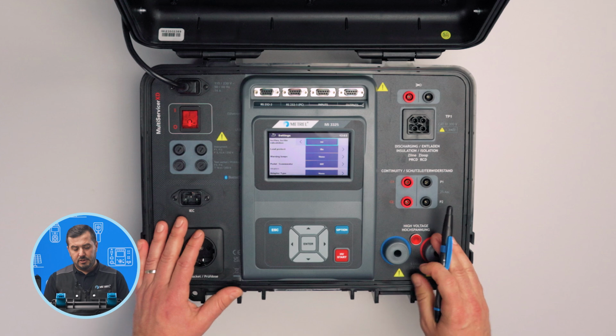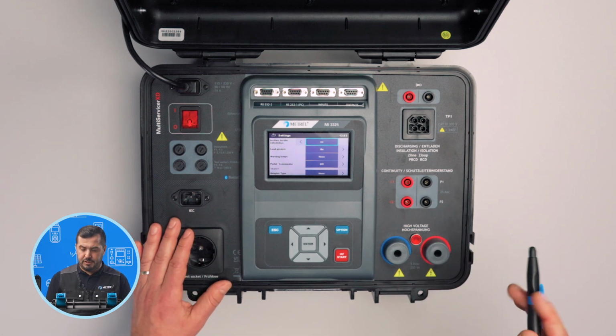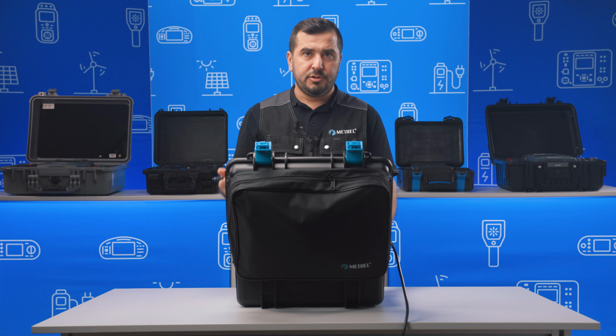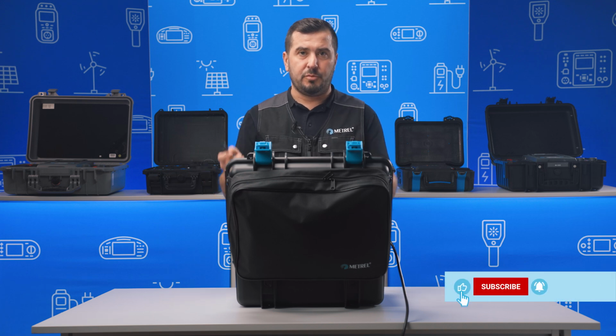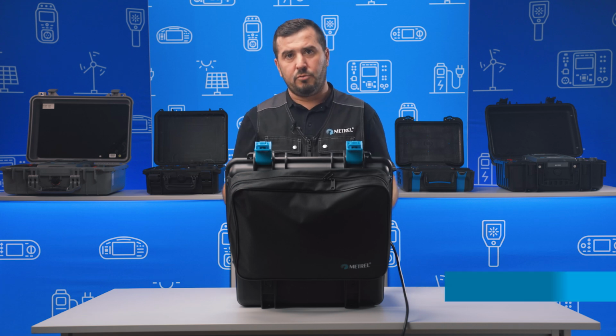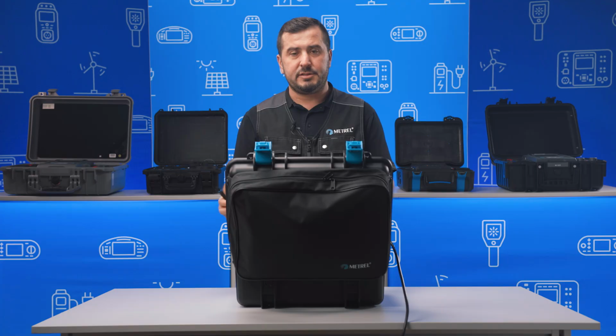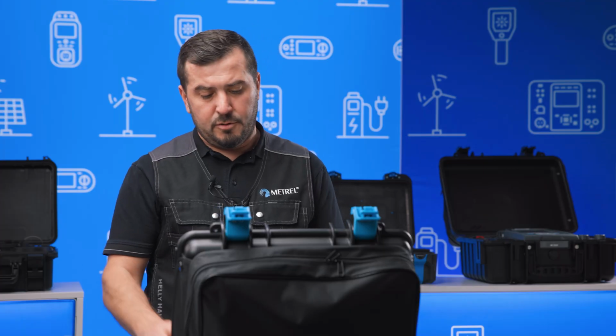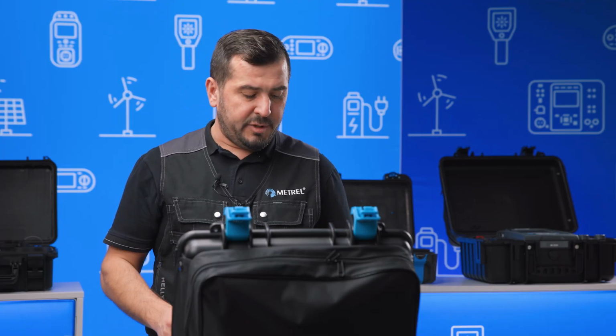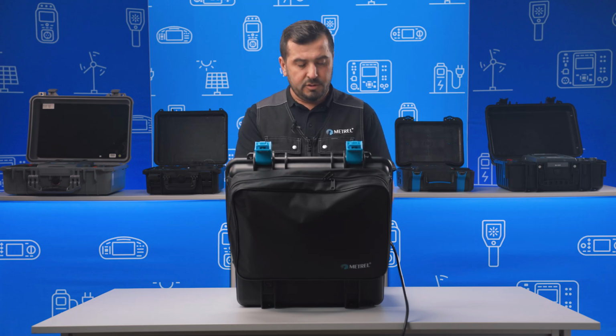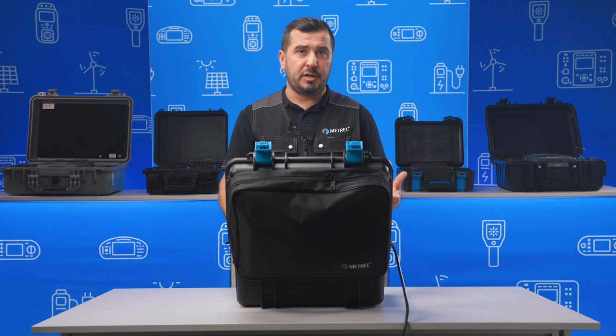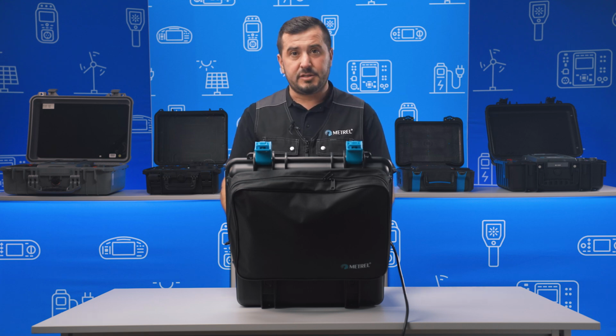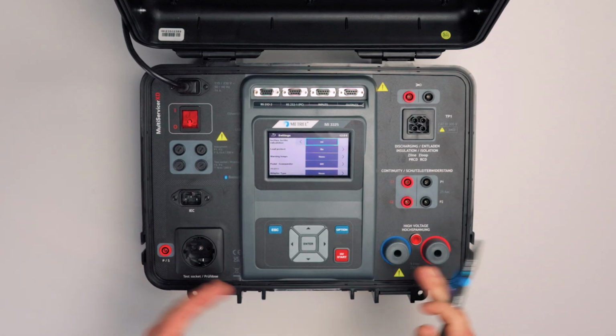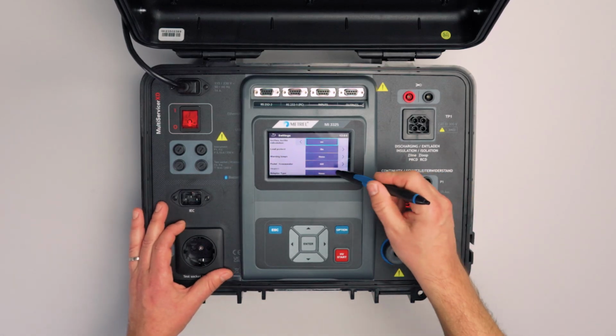The next one is to enable or disable load pretest. So in case that we have, for example, on the electrical installation, during the insulation resistance test, some loads installed between live and neutral, the pretest will warn us not to perform the test. But in case that we are testing mainly devices connected to the main test socket, we can also decide to disable this pretest, and, for example, in case of testing extension cords, we will not receive any of these warnings.